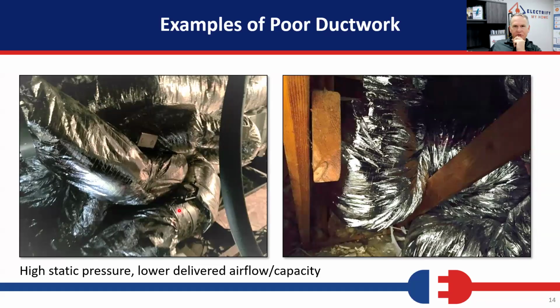Man, we see stuff all the time that's just crazy. Like this is a duct system with a bunch of home runs in it, and there's a bunch of dampers in this system. Like there's one here on this duct, there's one here, one here. They're just everywhere. So when we have all these small ducts, when we blow that plenum into smaller ducts and we don't use a large duct to transition into the smaller ones, there's a ton of takeoff resistance. In other words, all those start collars have like a 35-foot equivalent length. Just by the time the air gets into that start collar, it's already the equivalent of 35 feet of duct. Now, if I put a damper in there, which is going to cause static pressure, even if it's open, it's not going to be zero. It's not going to be crazy impactful.